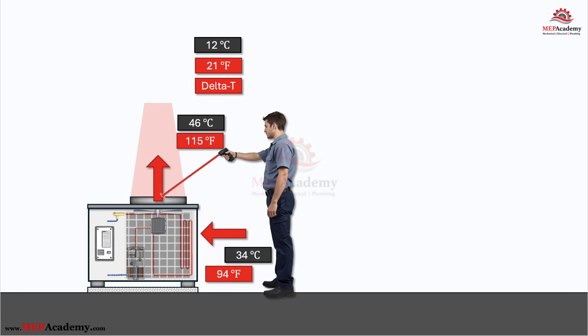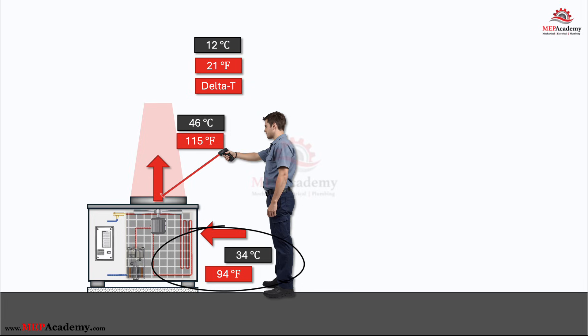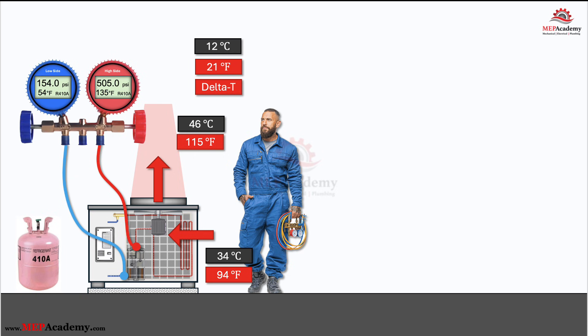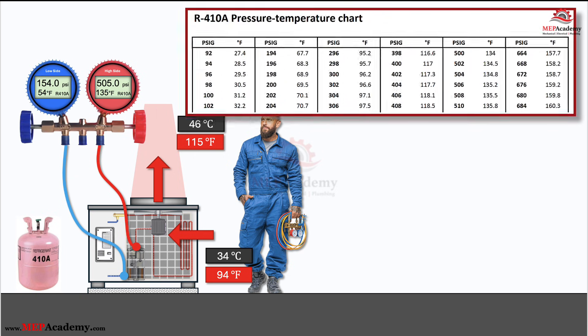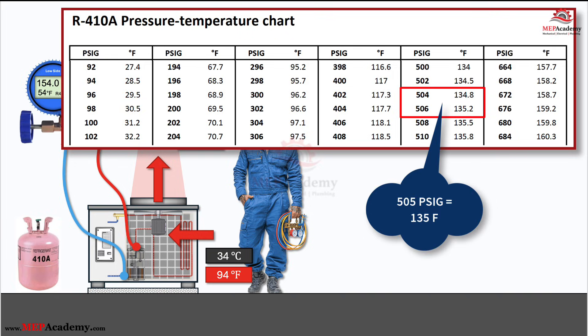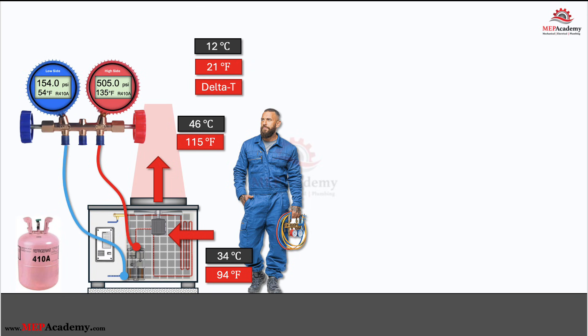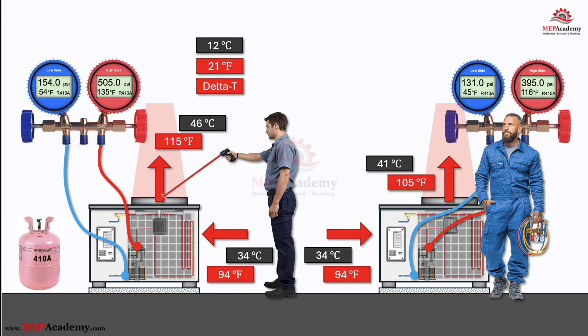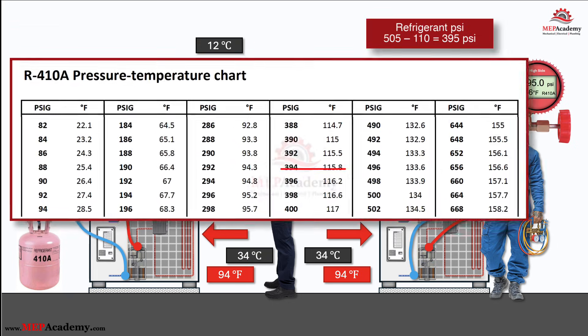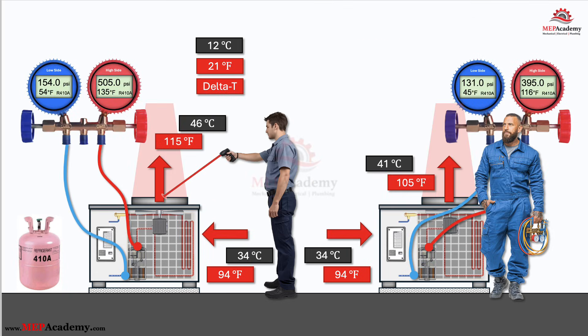Here's a side-by-side demo. First the quick method: ambient entering air equals 94°F, discharge air off the top equals 115°F, air delta T equals 21°F. Most techs say 'looks good' and leave. Now the real method: high side pressure equals 505 PSIG on R-410A. Using the pressure-temperature chart, saturated condensing temperature equals 135°F. Condenser temperature difference equals 135 minus 94 equals 41°F — the coil is dirty or airflow is low. After cleaning the condenser coil and removing shrubs suffocating air to the inlet, head pressure falls 110 PSI from 505 to 395 and the delta T numbers improve. The customer's bill drops 15% and the compressor thanks us. Air delta T barely moved, but the system was screaming.